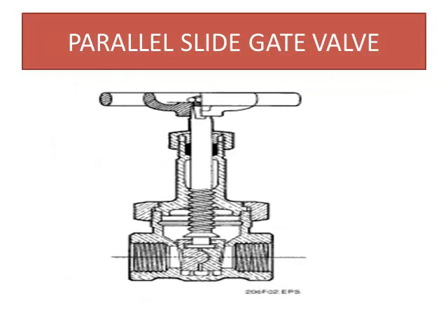This is a photo of a parallel slide gate valve. You can see that while opening and closing the valve, discs slide parallel to the valve seat. The parallel slide valve design relies on the primary system pressure acting on the downstream disc for seat integrity. There is no wedging action or extra loading on the seat. As a result, closing torques are comparatively lower, requiring less manual operating effort or smaller power actuators.